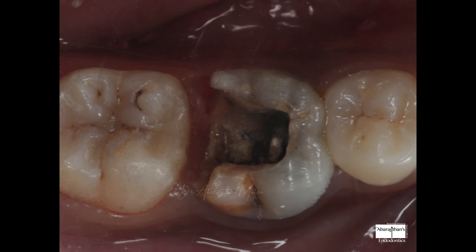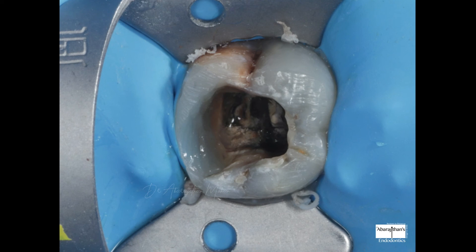The liquid in the pulp chamber should not contact the gingiva or any periodontal tissue. This apex locator gives a reading whenever the file contacts any PDL tissue — so if the canal is wet and the liquid contacts even the interdental papilla, it will give you a false reading. That is a major reason for inaccurate apex locator readings. We strongly recommend rubber dam; if not used, a pre-endodontic buildup is mandatory to get predictable apex locator readings.